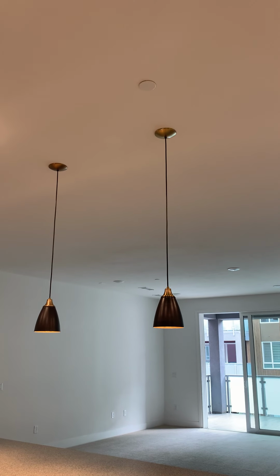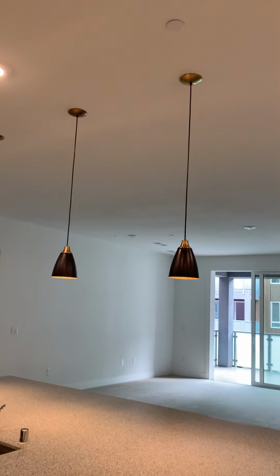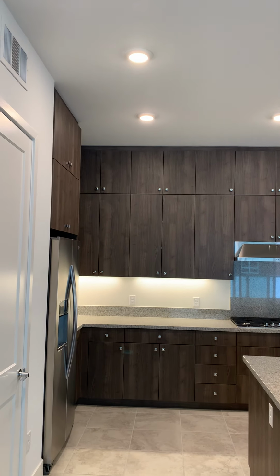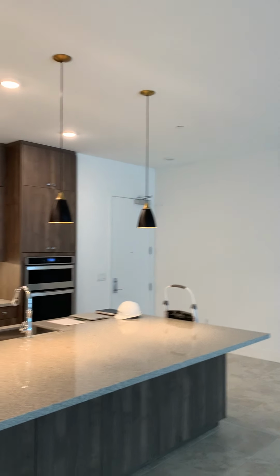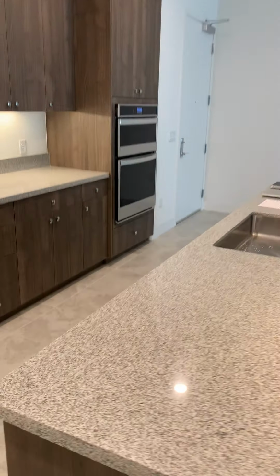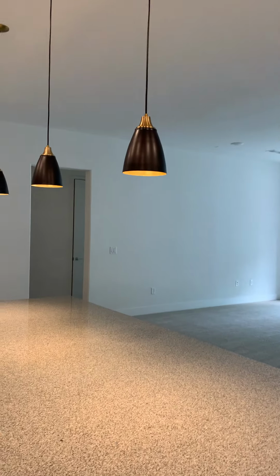Another thing about the fire sprinkler system is it is not linked to your smoke detectors, and your smoke detectors are found in every hallway and every bedroom, which is also code. So you have one in the hallway, you have one in the bedroom. Same thing with that hallway and the second bedroom. You'll notice there is not a smoke detector / carbon monoxide sensor in your kitchen because everyone's would be going off all the time. But they do have them in the hallways and in the bedrooms, which is code. So the smoke detectors / carbon monoxide detectors are not linked to the fire sprinkler system. Not linked. The alarm that is linked to the fire sprinkler system is the verbal sounding alarm in each bedroom.